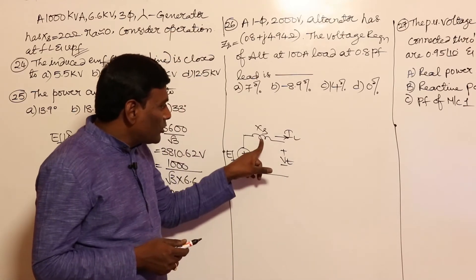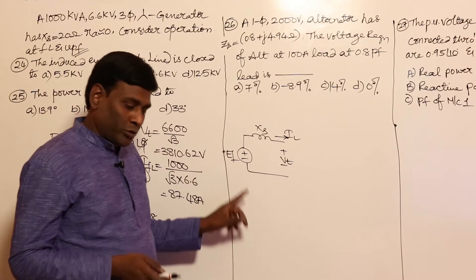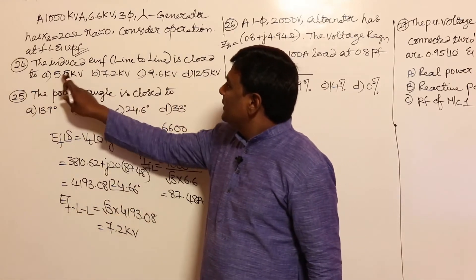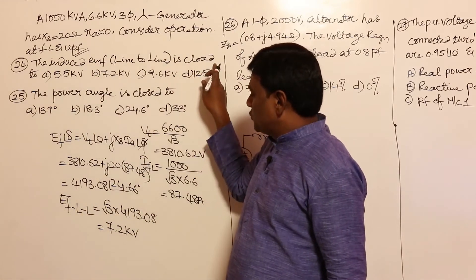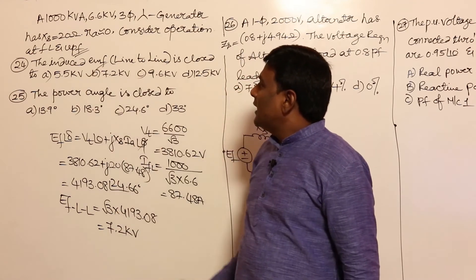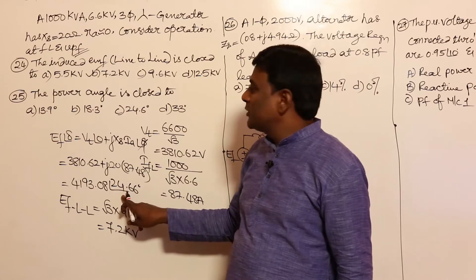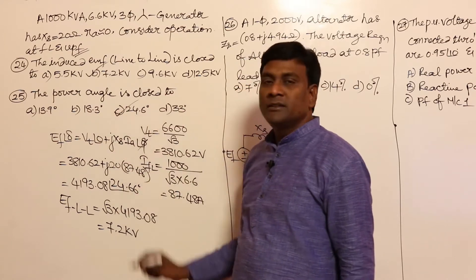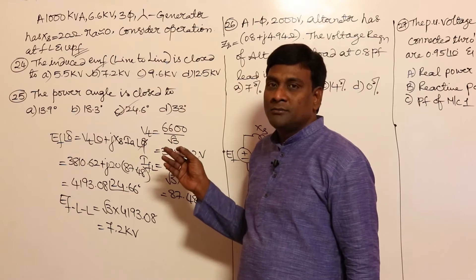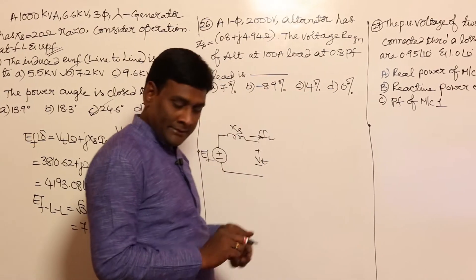So the induced voltage line-to-line is approximately 7.2 kV, and the power angle is approximately 24.66 degrees — about 24.6 degrees. That is four marks easily.